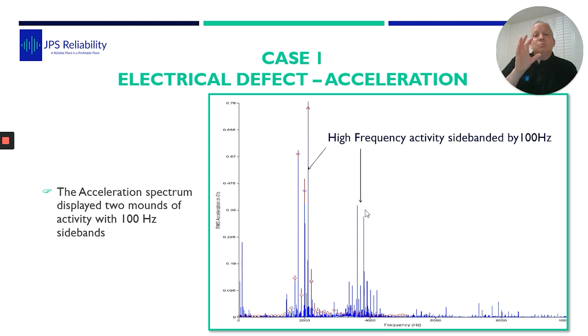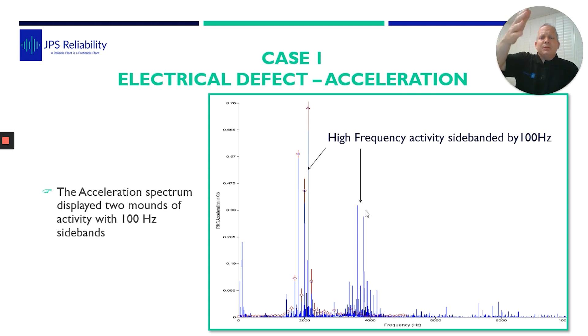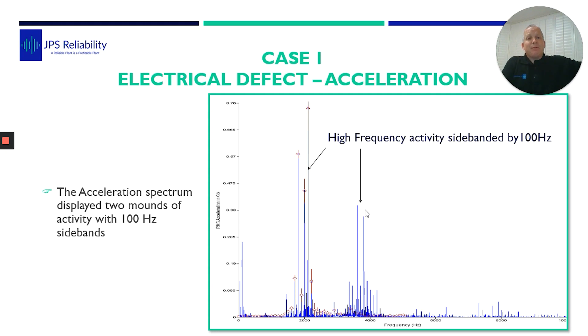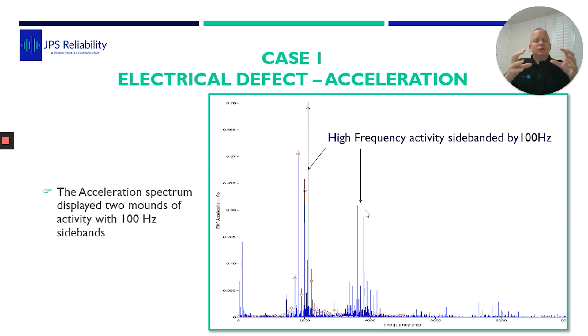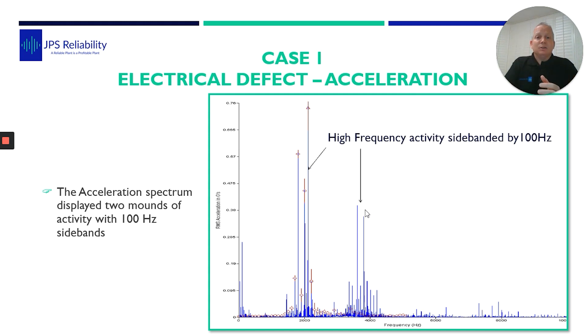And there's a point where you need to use your common sense. While I was there taking the vibration readings — touching, smelling, feeling — yes, the side of the motor was hot. But this is an electrical anomaly. This is a really large motor up on a pedestal. As I clamped the motor, I managed to touch the terminal end, and the actual power cable going into the motor was hot to the touch. So I said to them, I've got an electrical defect. If you're picking up your vibration, you can touch it and feel it — and the motor was bumping, missing the heartbeat as such. So it's not mechanical. Your bearings are okay; something electrical is causing the problem.